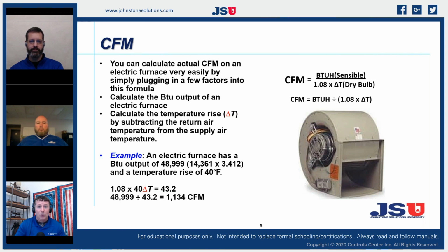Let's just say that: 1.08 times that temperature rise. So say this particular one, I had a 70-degree return and I had a 110-degree supply. I had a 40-degree temperature rise. So I just go 1.08 times that 40-degree temperature rise is 43.2. And so if I took my total BTUs that I had calculated, 48,999 divided by that 43.2, voila. I have the exact CFM that my blower is running.